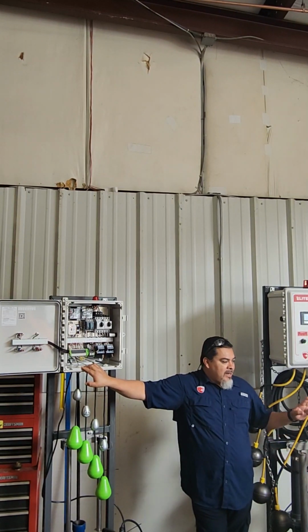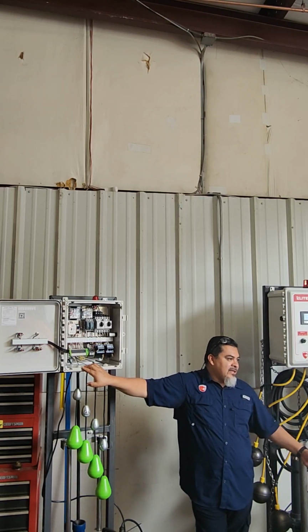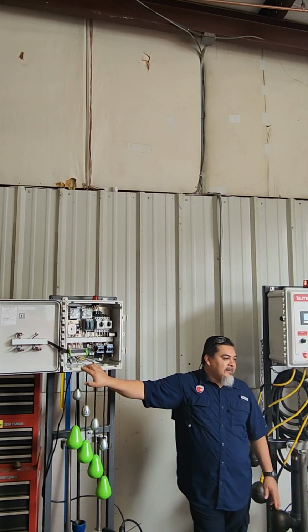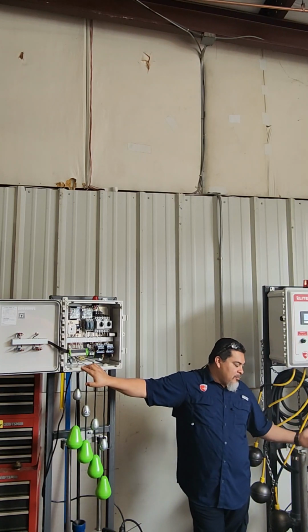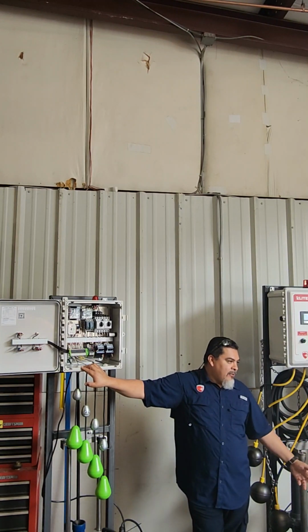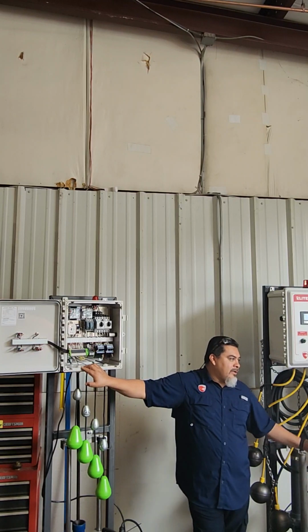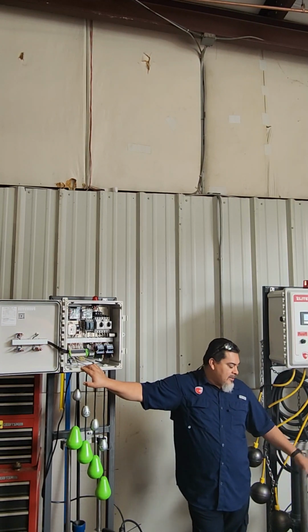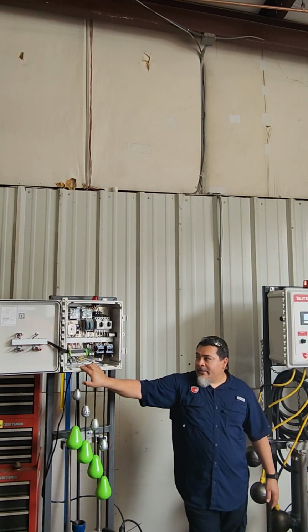You can leave it bypassed, but of course that's an indication that it's going to fail sooner or later. If it overheats, there's no protection. But it'll buy you time to get them a new pump, get the system up and running, or send one to get repaired, and whatever needs to be done to that pump to get it up to 100%. All right.